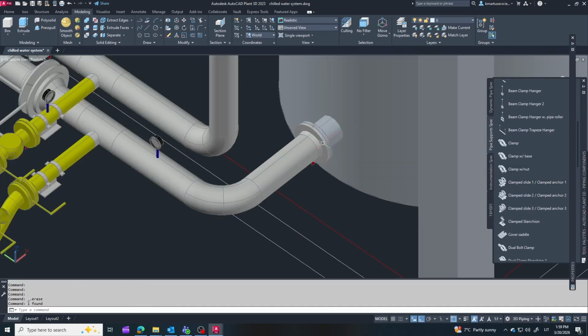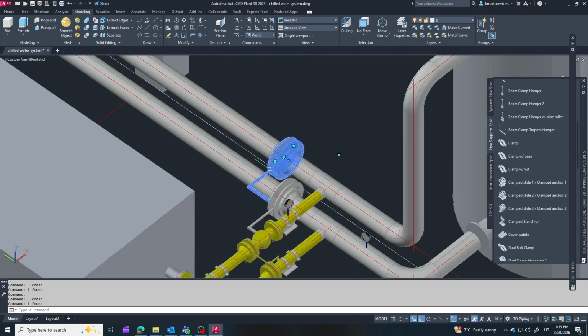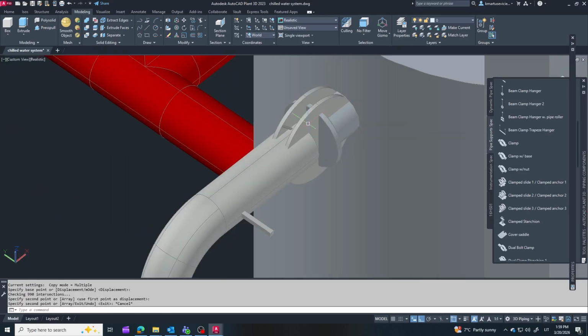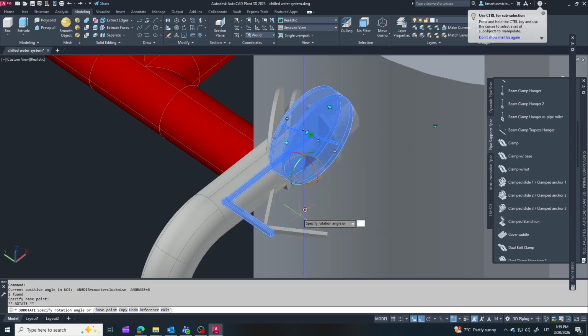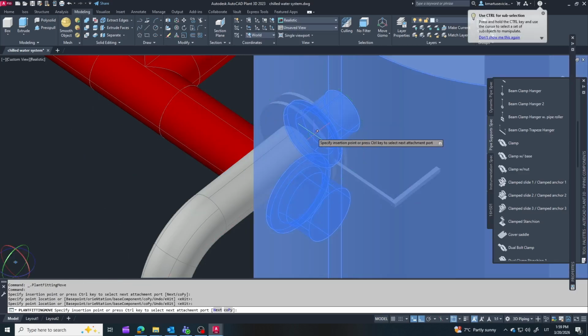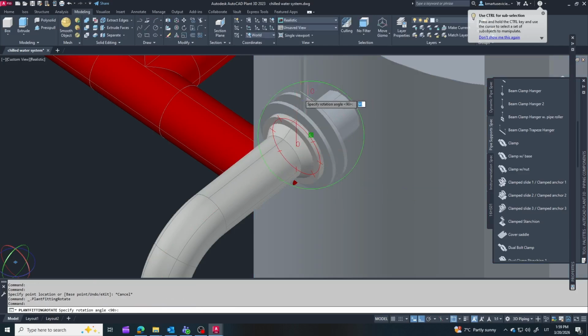I also add isolating valves directly on the buffer tank nozzles. For example, if the buffer tank needs inspection, cleaning, or repair, we can isolate it without shutting down the entire system.